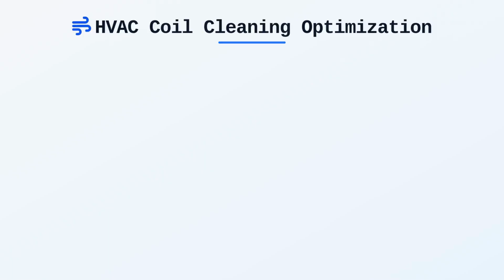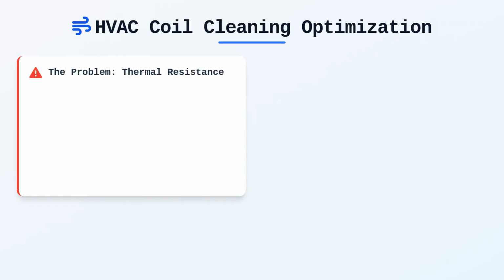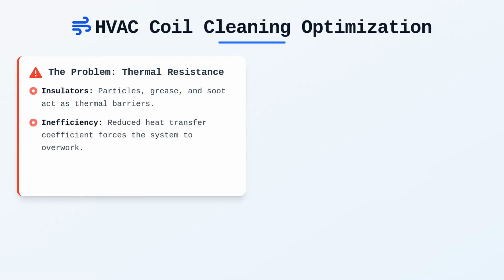Cleaning an HVAC coil is fundamentally about removing thermal resistance and restoring laminar airflow across the fin surface. Particles, grease, and industrial soot act as insulators that reduce the heat transfer coefficient, forcing the system to work harder to achieve the desired temperature set point.